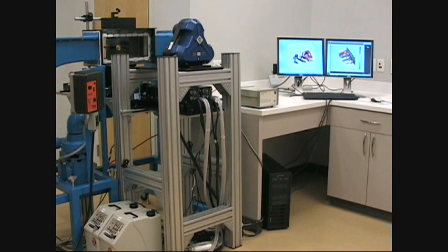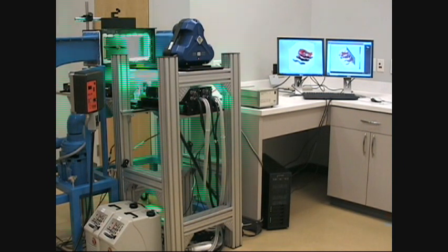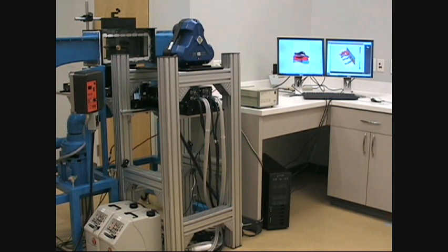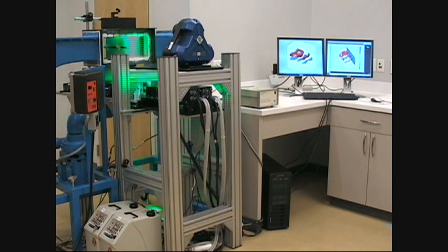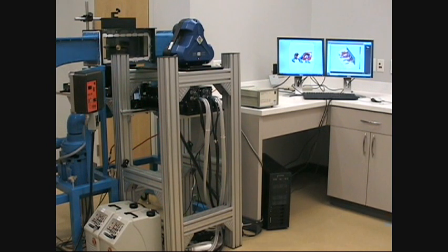One key aspect of the V3V system is the patented camera probe, which views the flow through three separate apertures. Here is an animation of the composite image as viewed by the camera probe. Individual tracer particles in the flow appear as a triangle or triplet pattern when viewed through the three apertures.